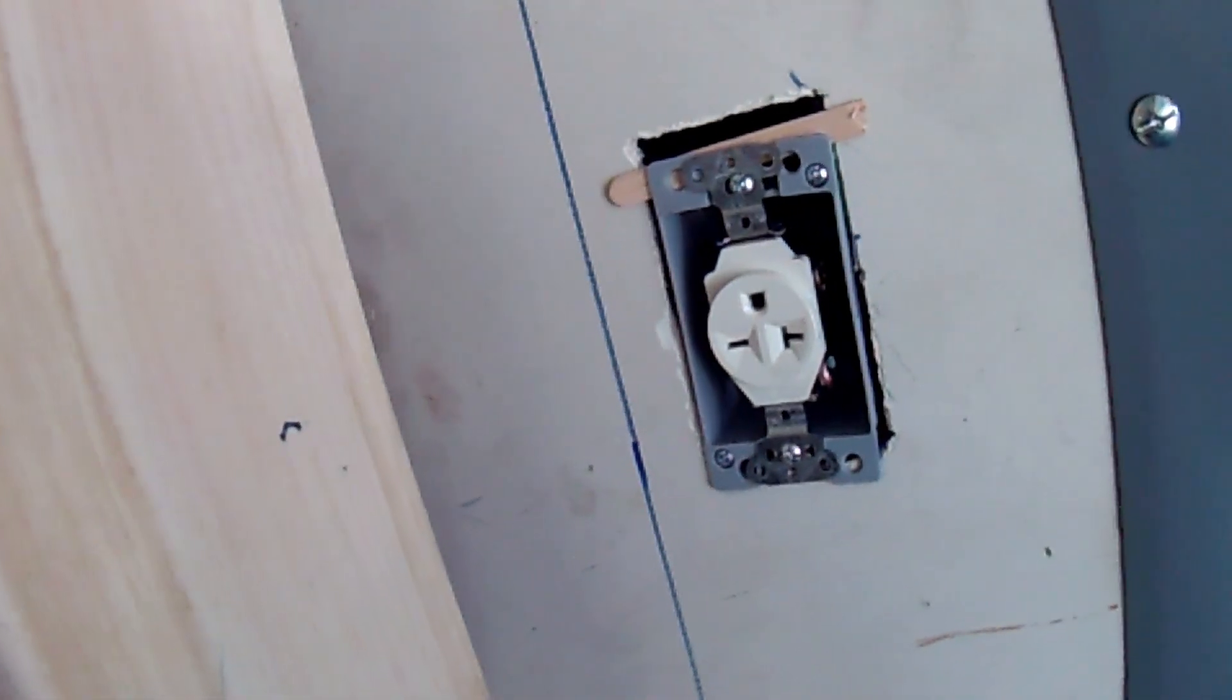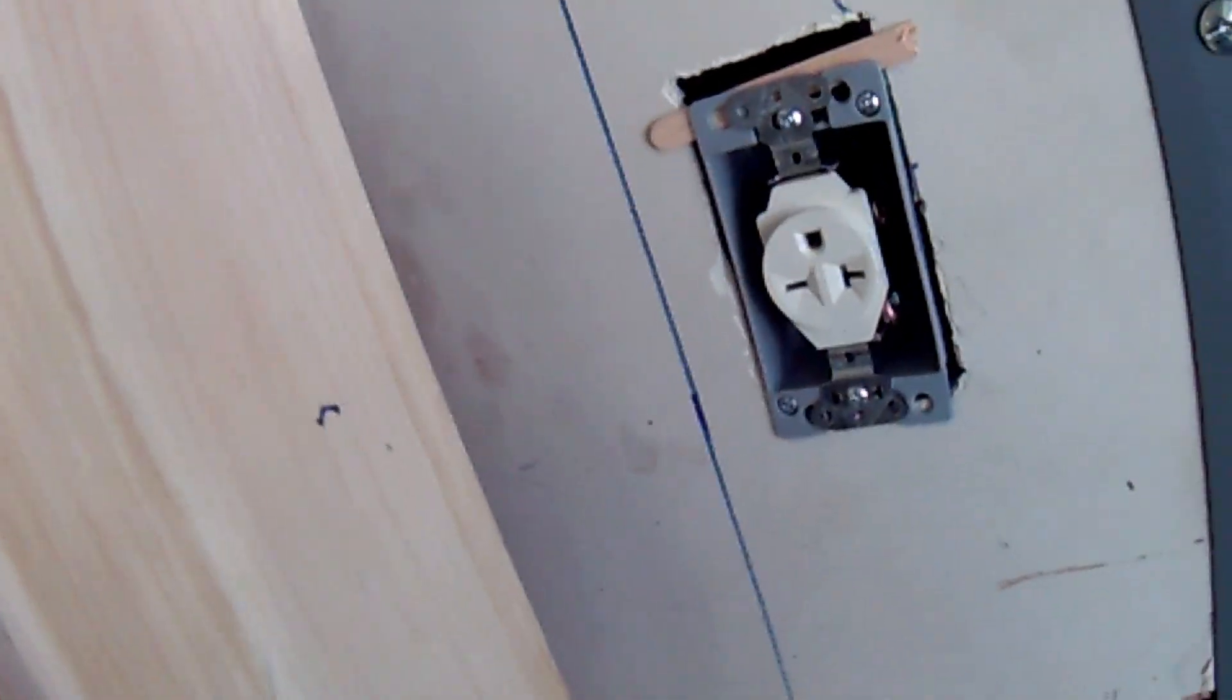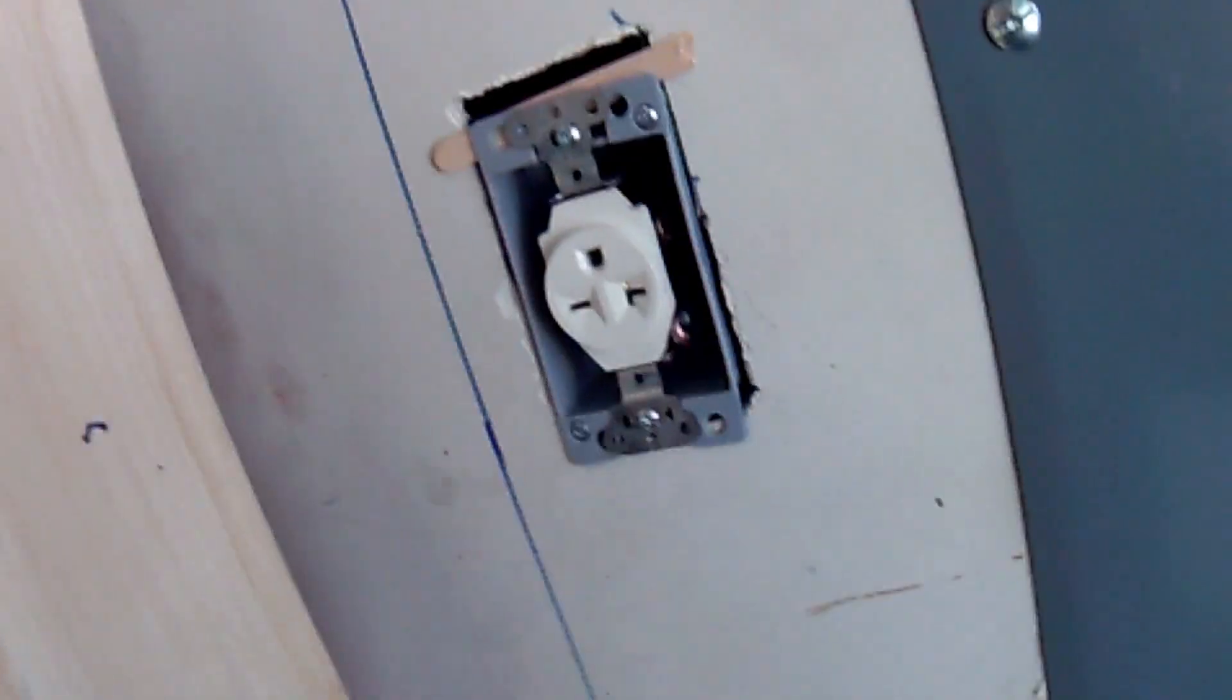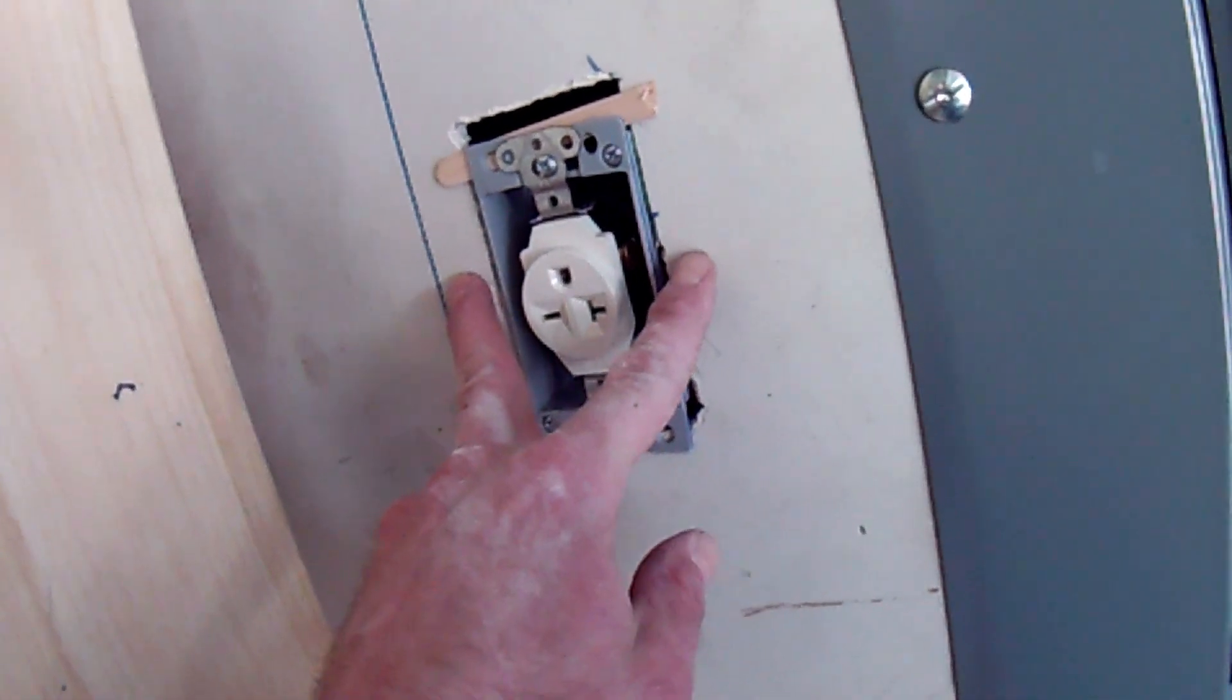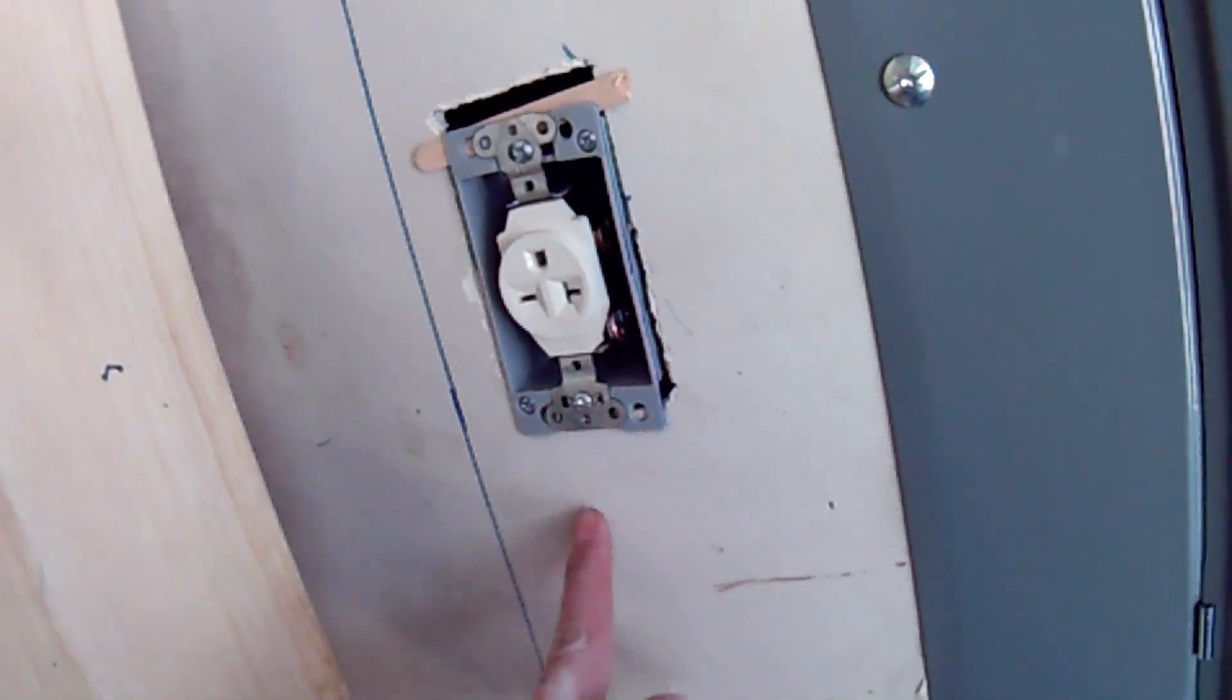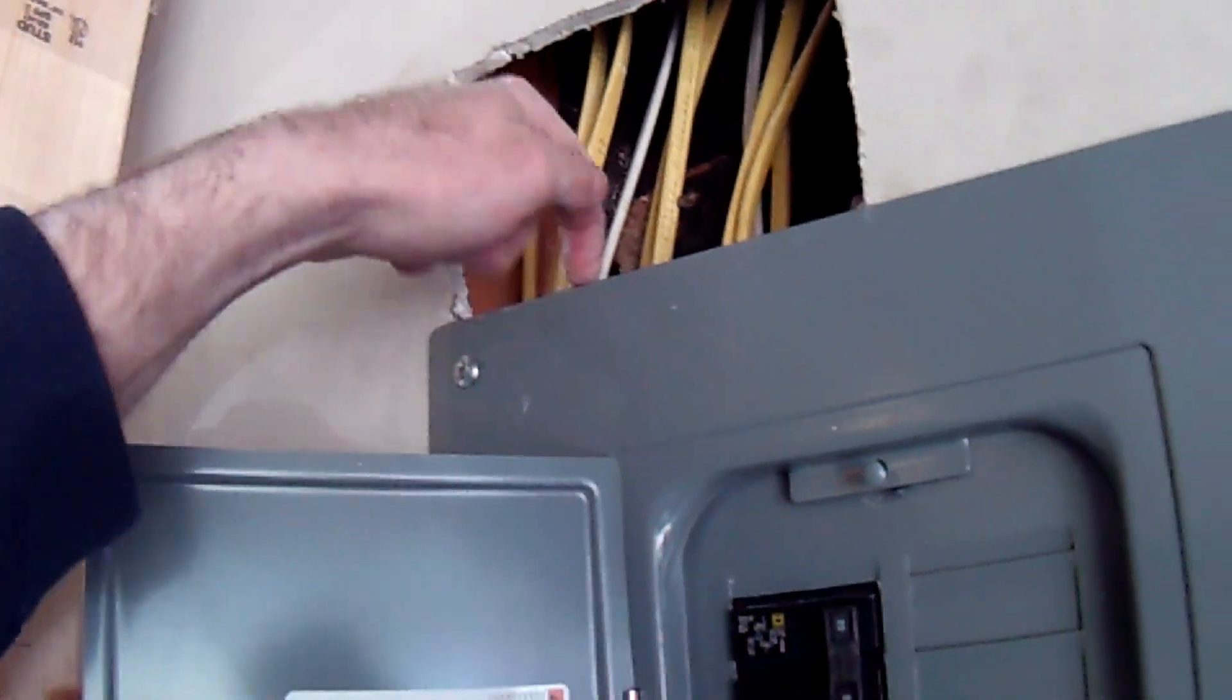But it has the two poles - the left leg and the right leg from the 220 - and the ground. I've already ran it up here, cut a hole through the 2x4, and dropped it down to the circuit breakers where I got a new circuit breaker here - 20 amp double pole, the Square D.